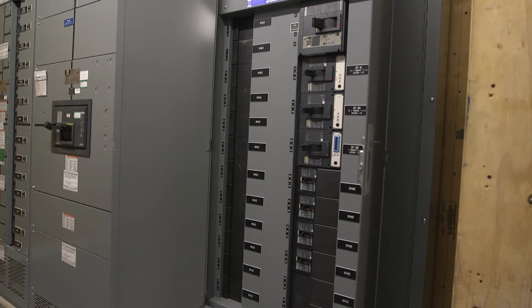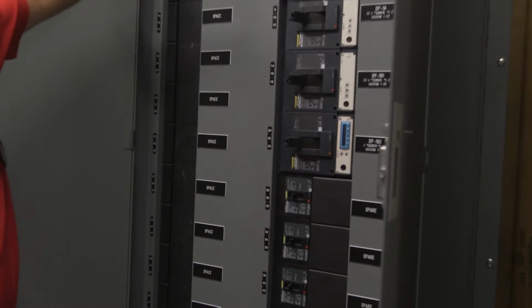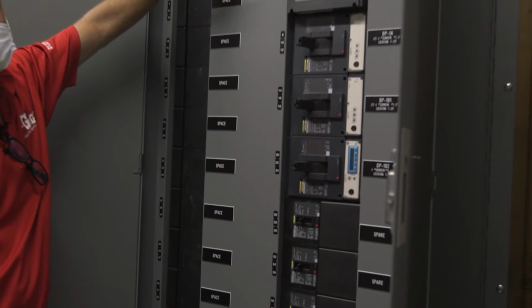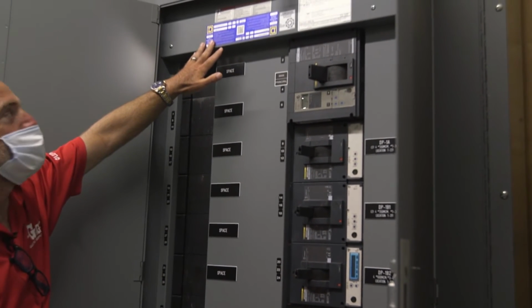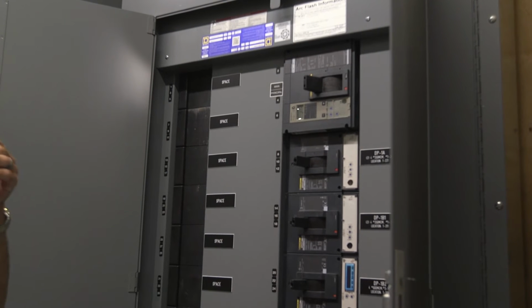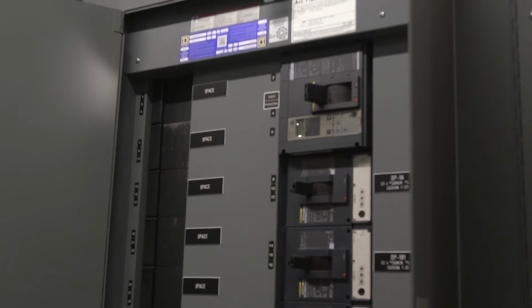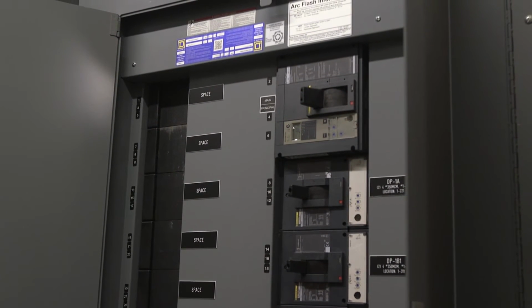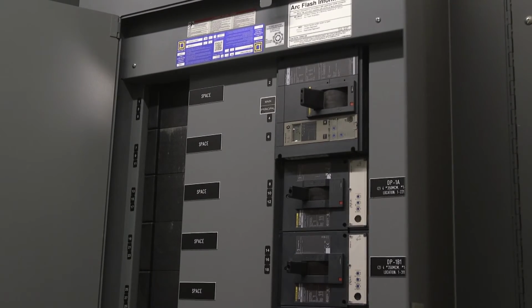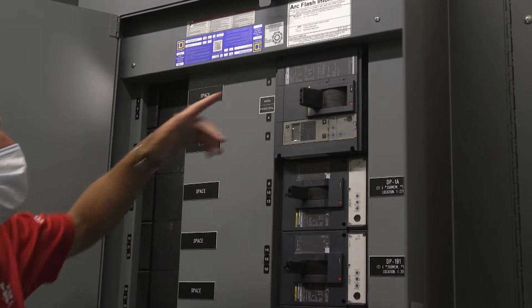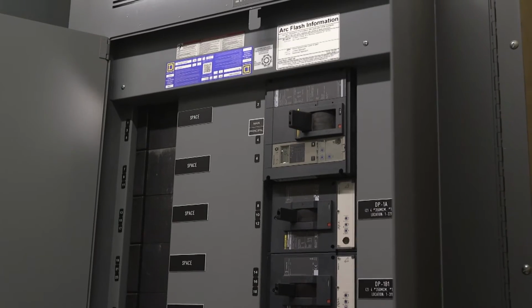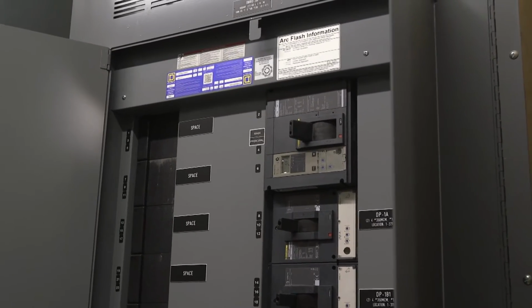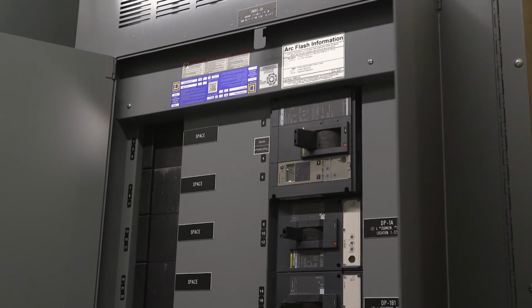So basically you have your nameplate, once again, that shows your amperage, voltage, and your Square D number, which is one of the most important things for maintenance and for replacement parts. Also, you have your arc flash label, which tells you your protective equipment that must be worn if you're going to open this board and do any work inside live.